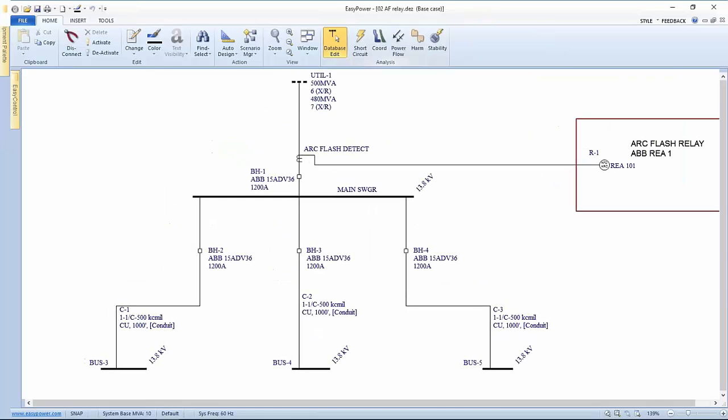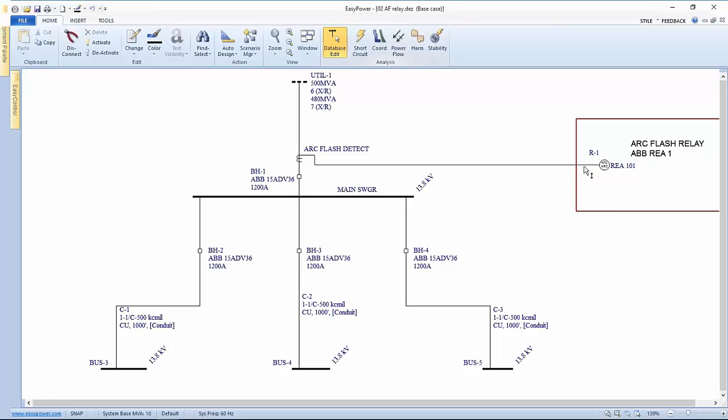In some cases, and we have had presentations by the ABB folks, there is a sensing for CTs to make sure that there's a certain minimum level of current in the switchgear before the arc light sensing is activated. But, for purposes of setup, I'm going to kind of ignore that. What I want to do is come up with some way to indicate that we are utilizing an arc flash relay and how we've got the set points, if you will, daisy-chained or hooked up.